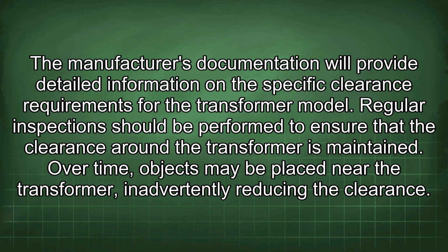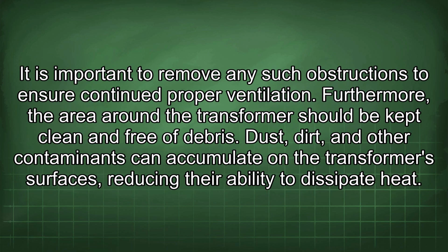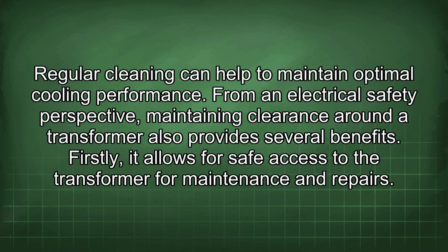Regular inspections should be performed to ensure that the clearance around the transformer is maintained. Over time, objects may be placed near the transformer, inadvertently reducing the clearance. It is important to remove any such obstructions to ensure continued proper ventilation. Furthermore, the area around the transformer should be kept clean and free of debris. Dust, dirt, and other contaminants can accumulate on the transformer's surfaces, reducing their ability to dissipate heat. Regular cleaning can help to maintain optimal cooling performance.